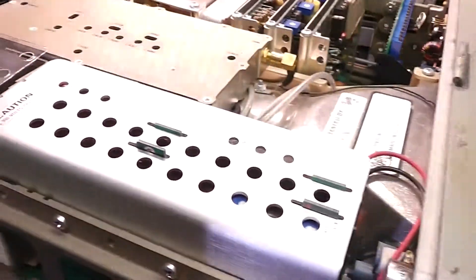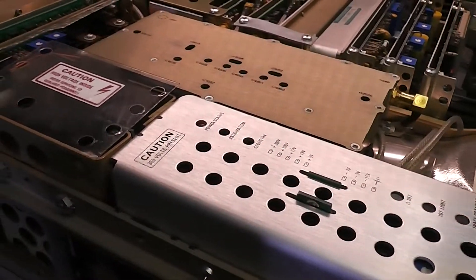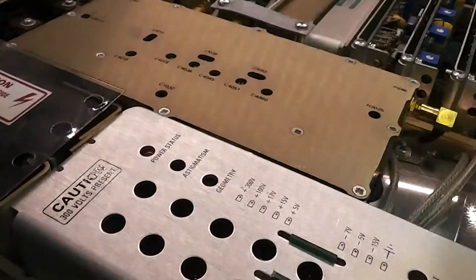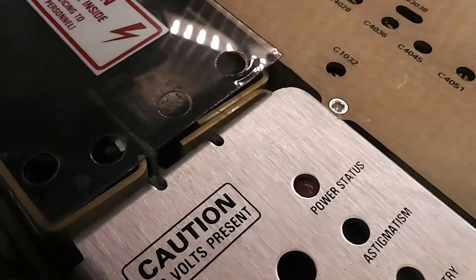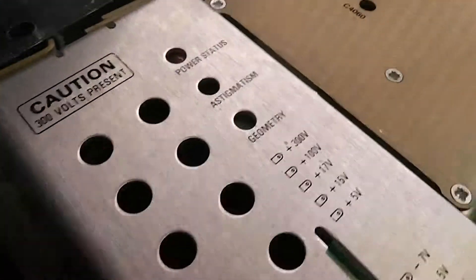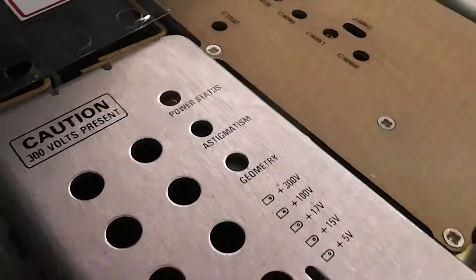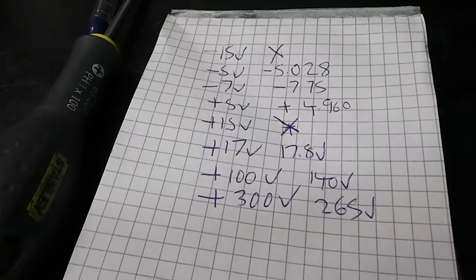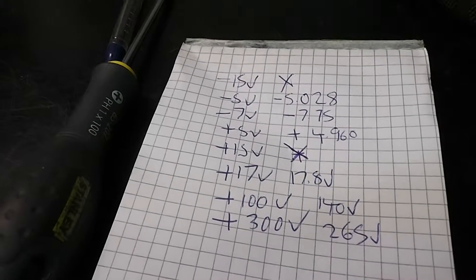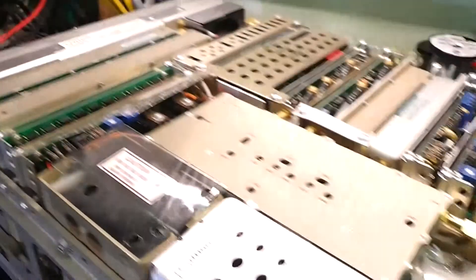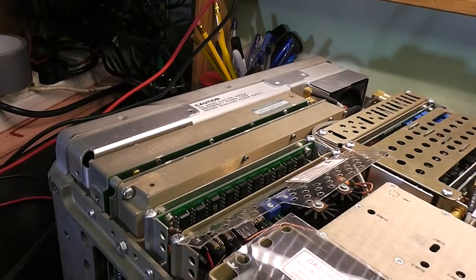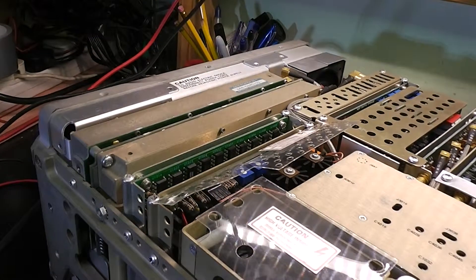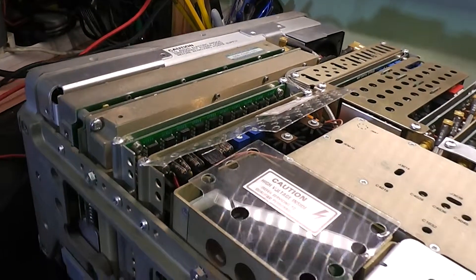Just looking in this wonderful amount of plumbing and electronics, the power status is showing red and indeed having a look at the voltages appear to have a missing minus 15 and plus 15, so looks like there's been a power supply failure but whether that's caused by something else shorting the power supply out I don't know at this time.